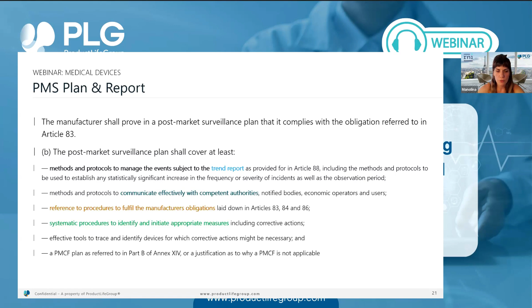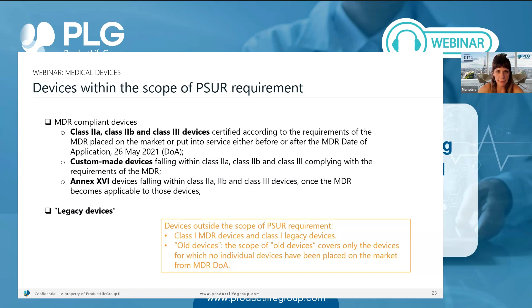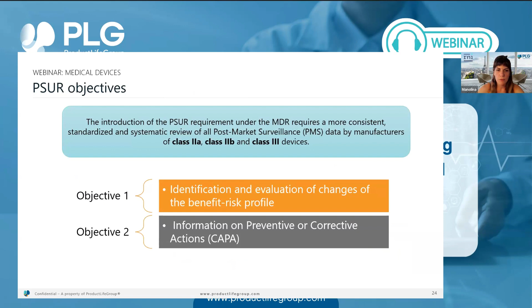And later on is about periodic safety update reports, which, as we said, apply to Class 2A, Class 2B, and Class 3 medical devices, and also custom-made devices with the same classification, and also Annex XVI devices falling under Class 2A, 2B, and Class 3. Also, legacy devices. The objective of the PSUR is to identify and evaluate if there is any change of benefit risk profile and to give information on preventive and corrective actions. Here is a guidance on periodic safety update reports from MDCG that was published in 2022, and we can follow this guidance in order to set up and clearly meet all the requirements for this PSUR assessment.